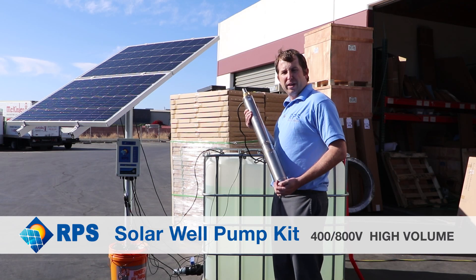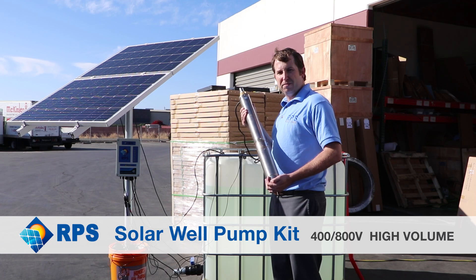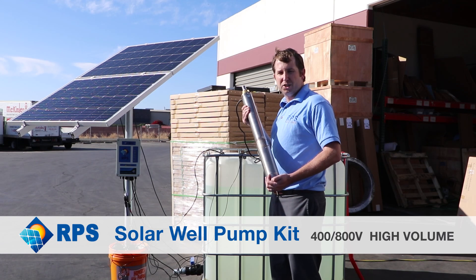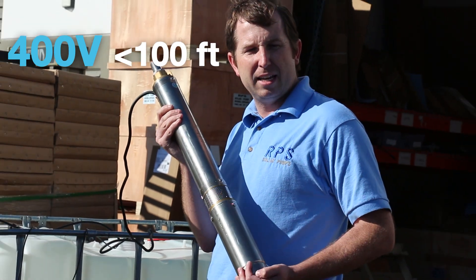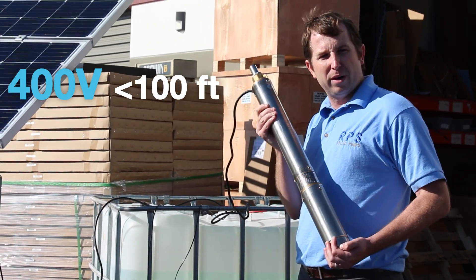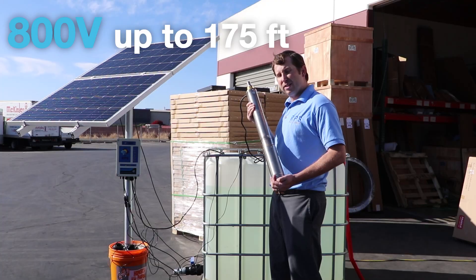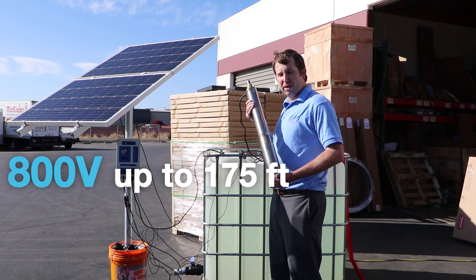These solar pumps operate off of anywhere from 400 or 800 volts. We call them the 400V and 800V — V for volume. If you're looking for pumping depths less than around a hundred feet of head at up to 10 gallons a minute, the 400V will be perfect for you. If you want a little bit more head, say up to 175 feet at around 8 to 10 gallons a minute, then the 800V will be perfect for you.